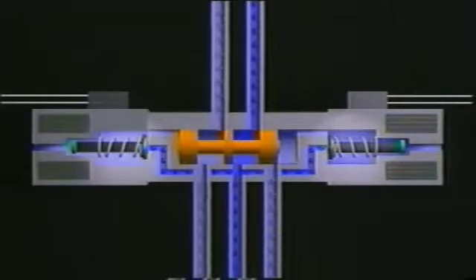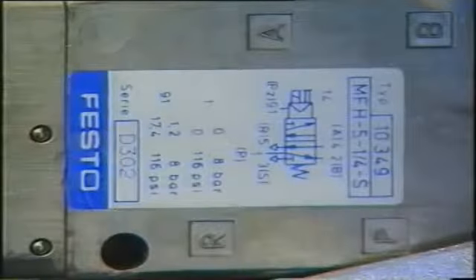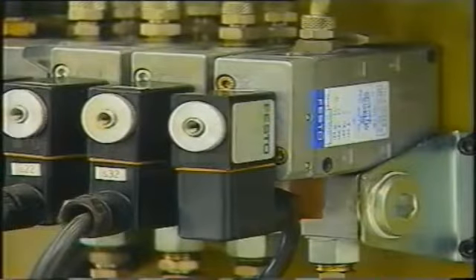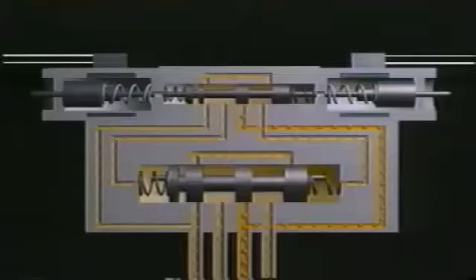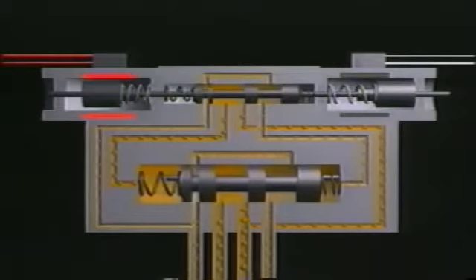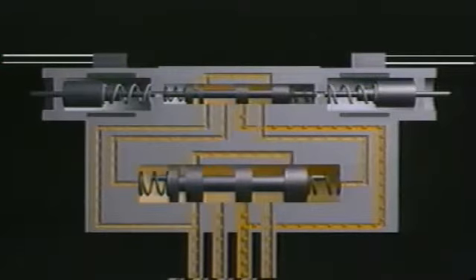Pilot-actuated double solenoid valves are also used. In electro-pneumatics, pilot control is used to allow solenoids with minimum possible power to be switched by an electronic controller. In electro-hydraulics, only larger directional control valves are pilot-actuated, and these are driven electrically via a relay or contactor. The reason? Smaller solenoids are cheaper, and the solenoid valve is cheaper overall.